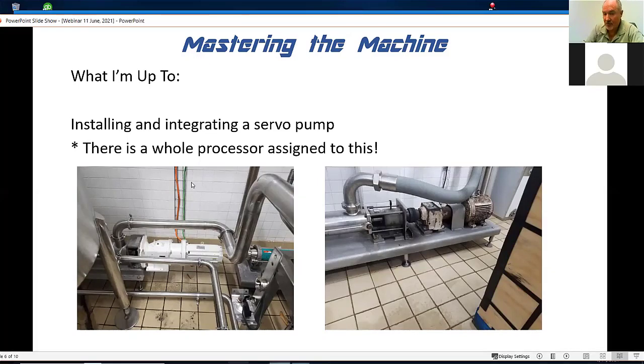This goes to another room. The servo card that drives this, to be able to do this, we had to put a whole new processor in here because the drive this runs on was far too new for the other processor we had. We had an L63, an older Allen Bradley processor, and had to use an L70, a newer processor with newer software to drive this. So we have one PLC rack with 2 different processors in it.